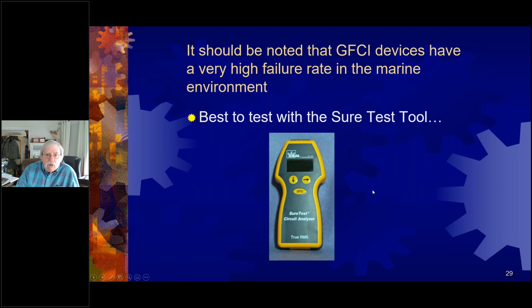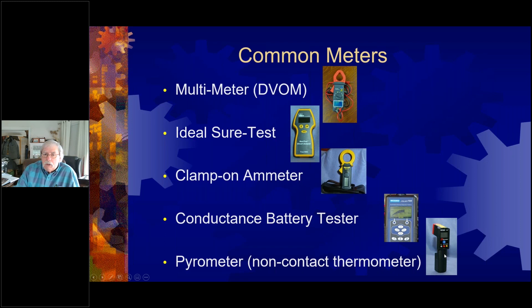One tool I recommend surveyors have is a Sure Test circuit analyzer — you can test GFCIs with this. What other tools? A DVOM, a clamp-on ammeter with the ability to measure AC leakage current, a conductance-type battery tester, and at the very least a pyrometer that can measure temperature.